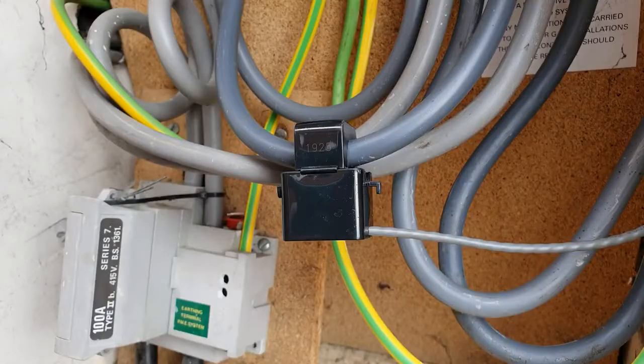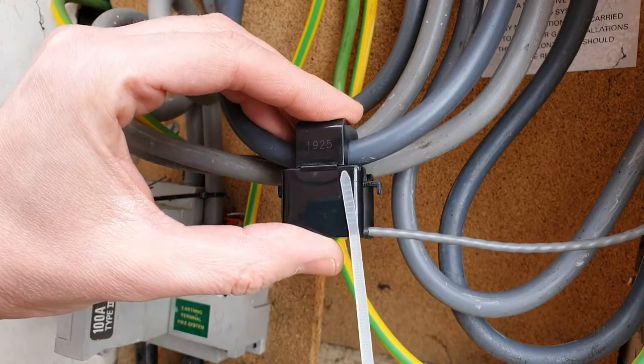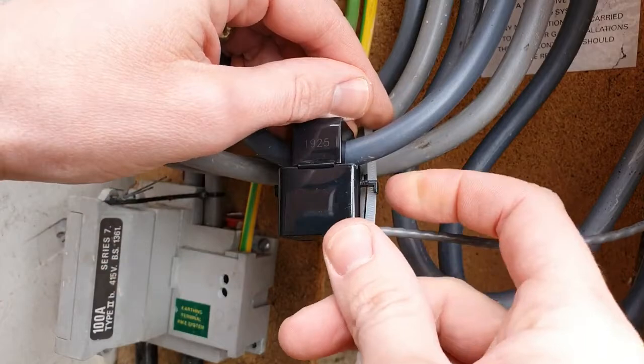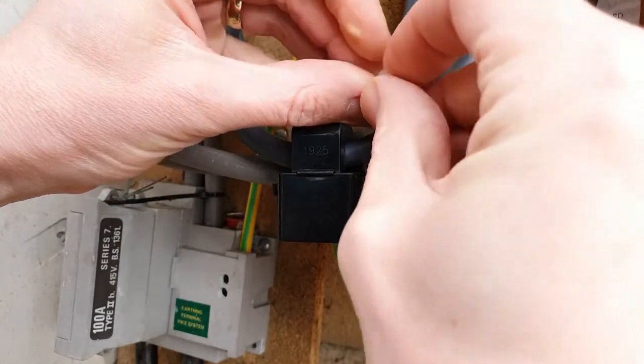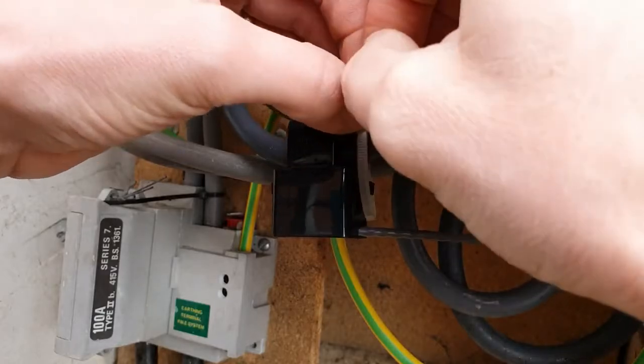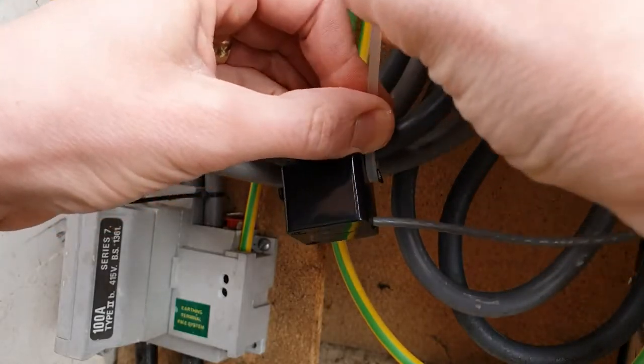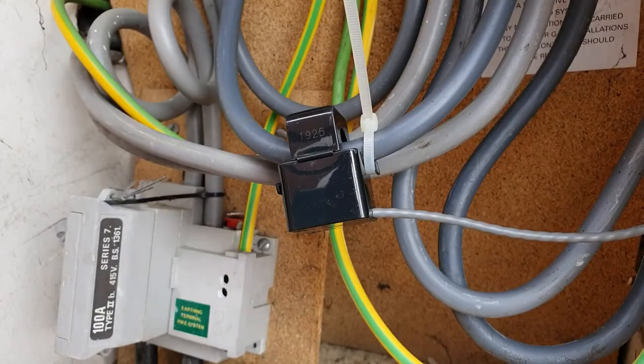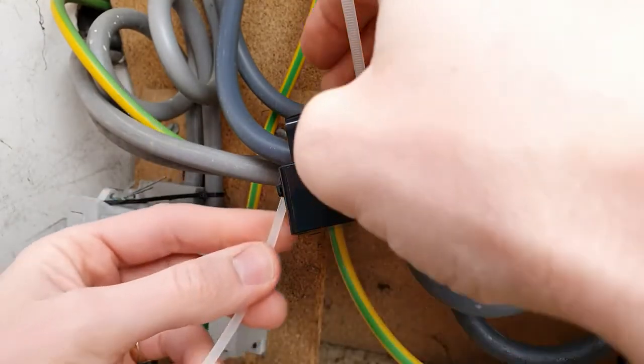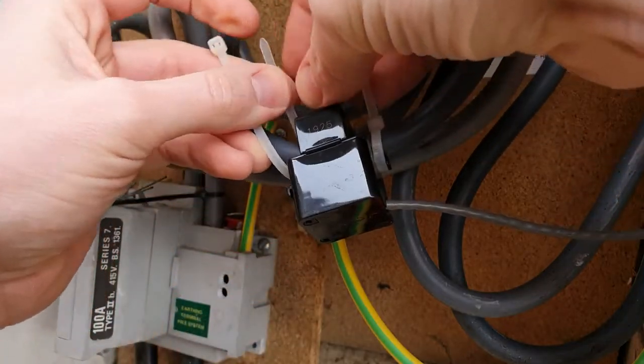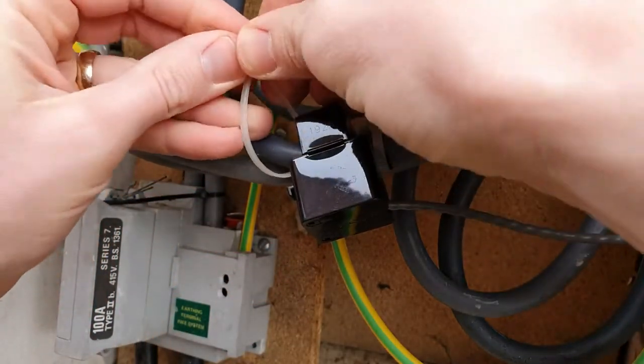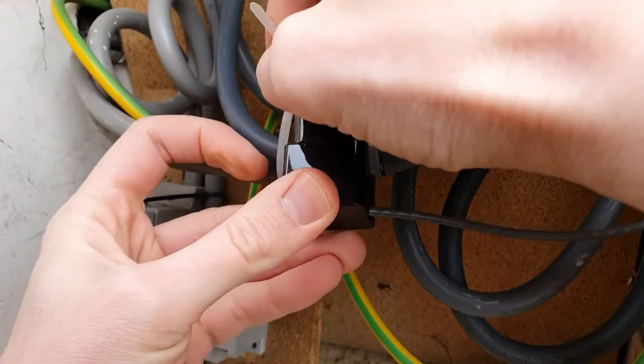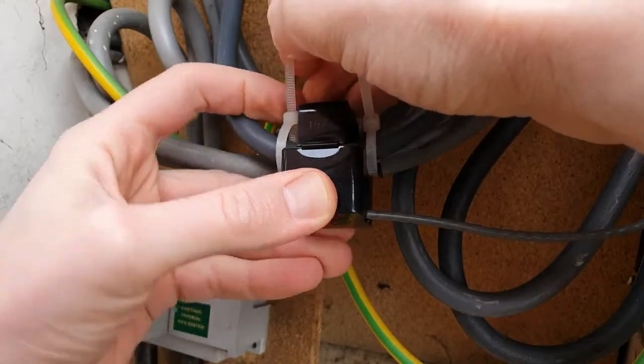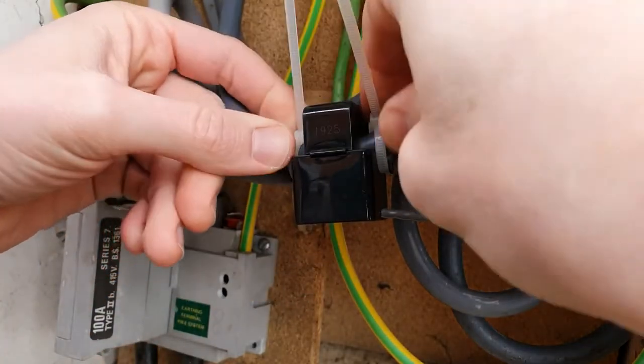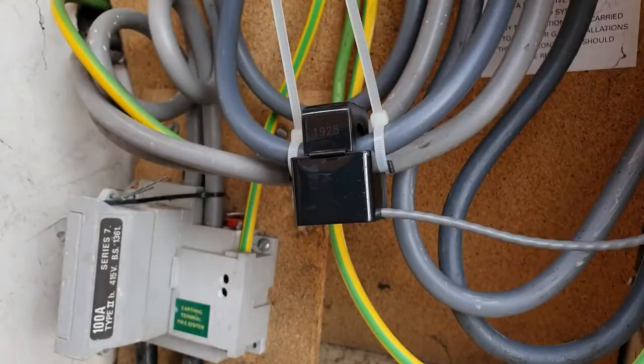So as we said earlier on in the video, it's best practice to connect the current transformer onto the meter tail using cable ties. So these little tags here have been designed to accommodate a cable tie, and we very simply just pass that around the meter tail and then pull it tight into there, and you can see that that's going to hold that nice and firmly in place. We'll pop one on the other side as well, so I'll just pop that around there like so, get that started through the cable tie, and then we'll just tighten that up, and as it does so, you can see that holds that nice and firmly in place onto our meter tails, and then it's just a matter of snipping off the ends and that's installed.